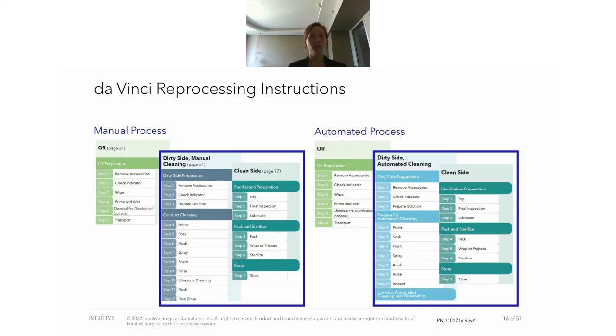The main difference for the automated cleaning is that a washer disinfector is being used, and you've seen some great pictures in the previous presentation with a load carrier that is utilized for the cycle. And if you go back to the manual cleaning, no washer disinfector is used. However, an ultrasonic is mandatory, while for the automated process, an ultrasonic is not mandatory from our side. It is optional to be used.